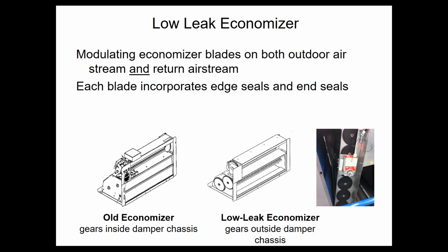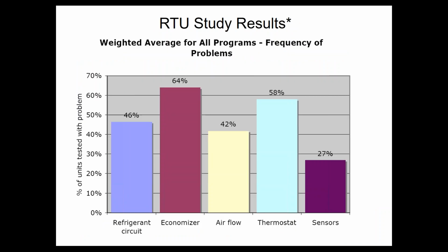Because when they're on the inside of the airstream, the problem is they can't be perfectly tight because they're gears and they have to move. So now the gears are on the outside of the airstream. So it's pretty visually easy to inspect that and see that. But you have to have low leak economizers, or some manufacturers might call them ultra low leak economizers.